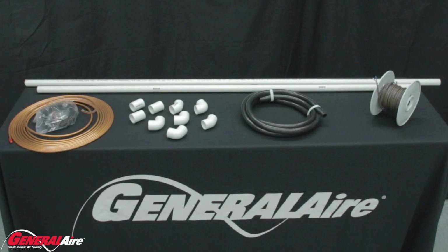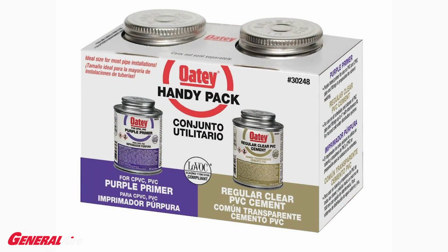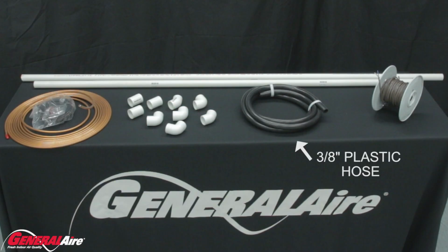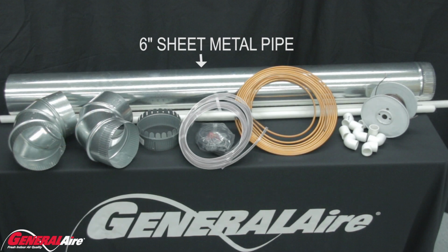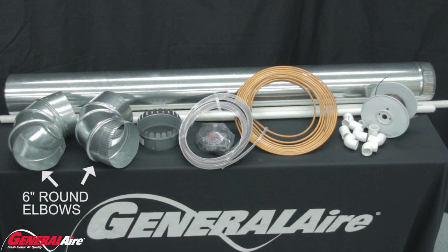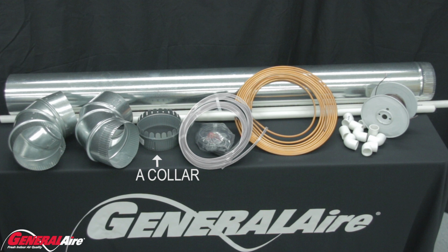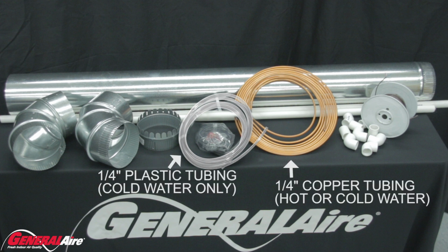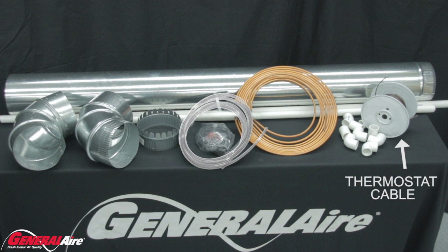Items not included in the box you'll need for the installation are 10 to 20 feet of 3/4-inch PVC rigid pipe and several 3/4 PVC fittings like elbows, T's, and 45 angle. You should have PVC glue and primer on hand also. Instead of PVC, you have the option to use 3/8 plastic hose as your drain line, a 5-foot piece of 6-inch round sheet metal pipe, and a couple of 6-inch round elbows, and an A-collar, 1/4-inch copper tubing or 1/4-inch plastic tubing for water supply, 20 feet of 18-2 thermostat cable.